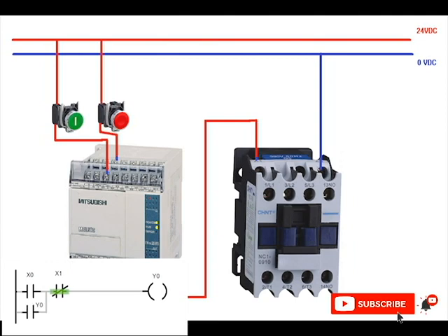If I press the green button with the normally open contact once, it will energize the output coil at Y0, because the path is completed, as I have used a normally closed contact for the stop switch. Now if I release the green push button, the output coil stays energized, as now the path to the output coil is closed via its own normally open auxiliary.